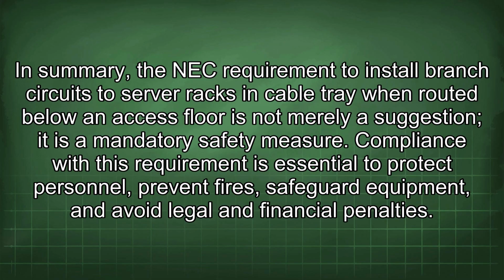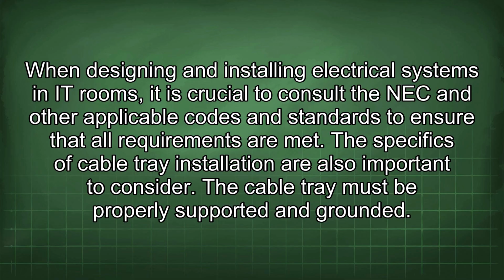In summary, the NEC requirement to install branch circuits to server racks in cable tray when routed below an access floor is not merely a suggestion. It is a mandatory safety measure. Compliance with this requirement is essential to protect personnel, prevent fires, safeguard equipment, and avoid legal and financial penalties. When designing and installing electrical systems in IT rooms, it is crucial to consult the NEC and other applicable codes and standards to ensure that all requirements are met.